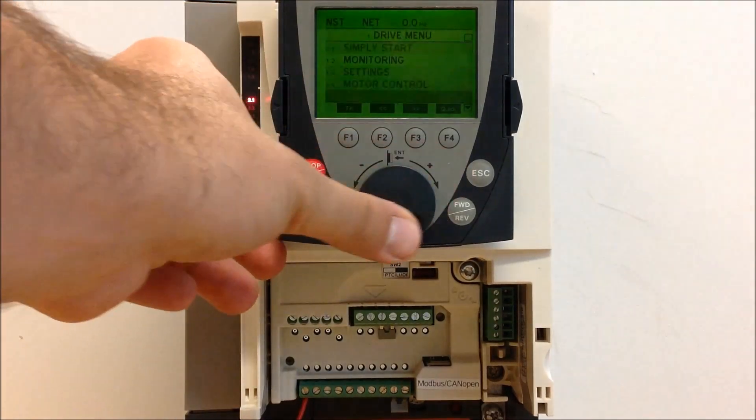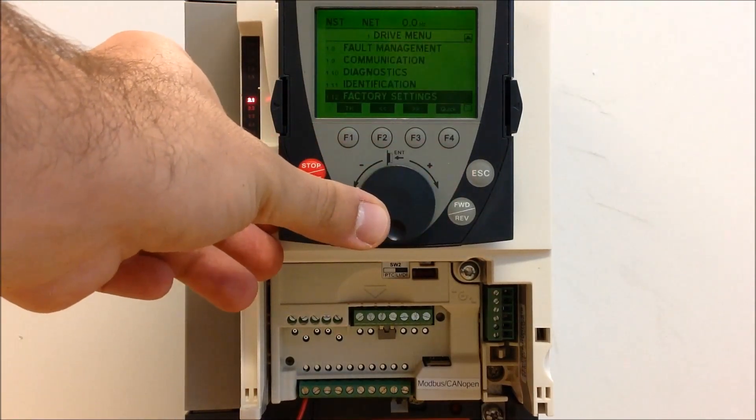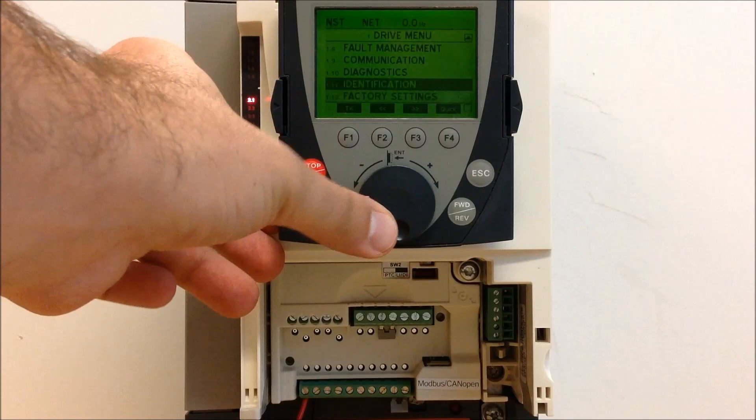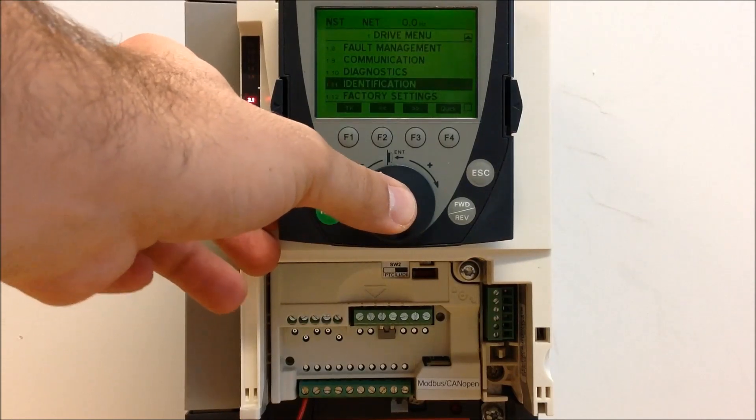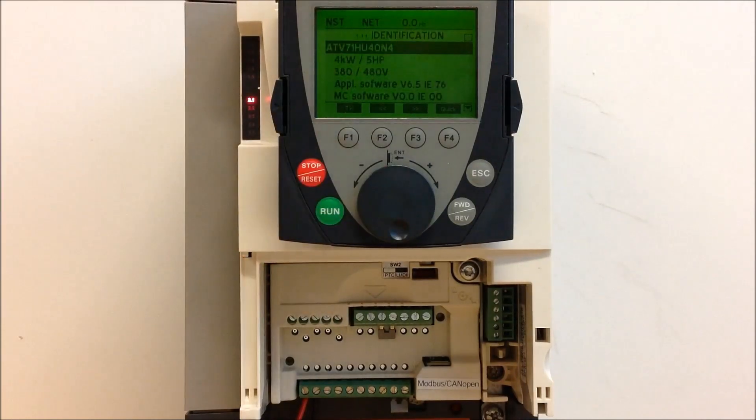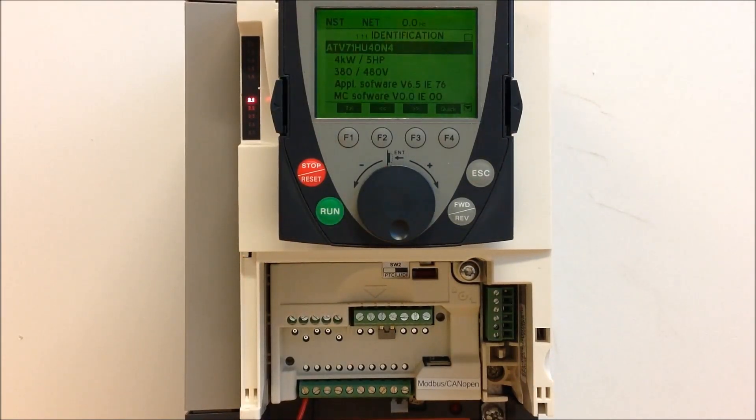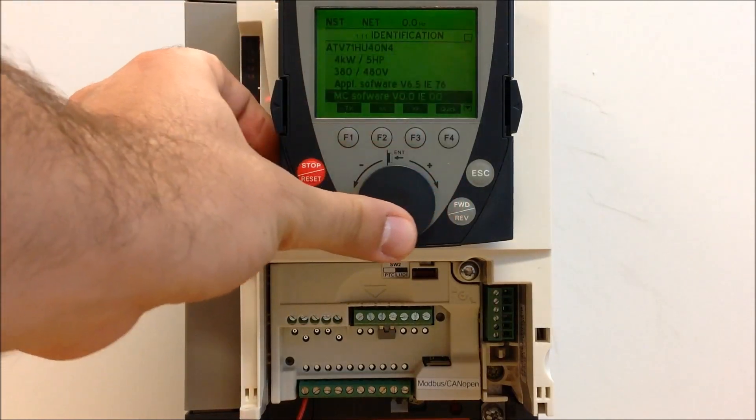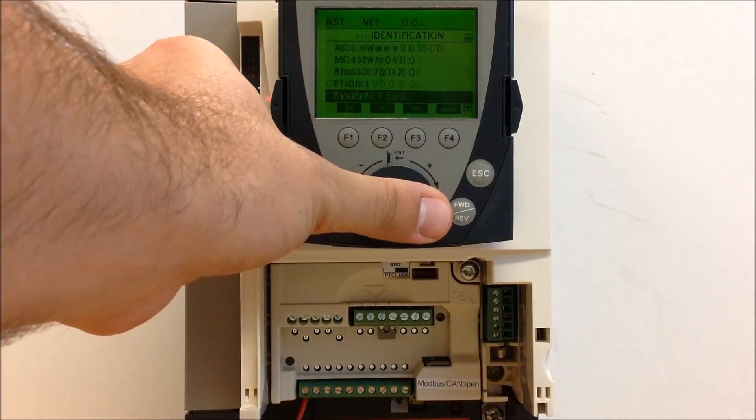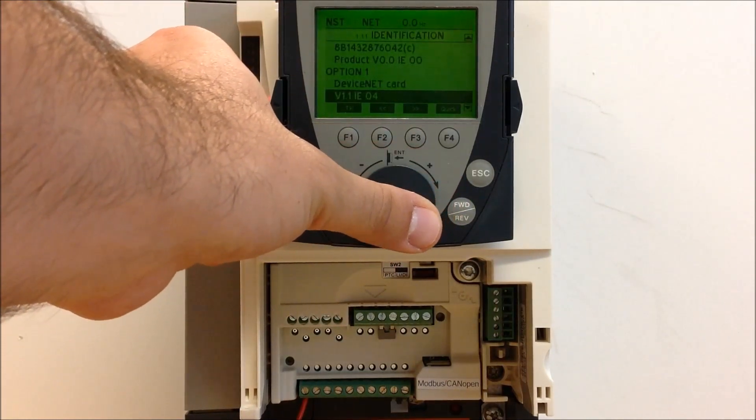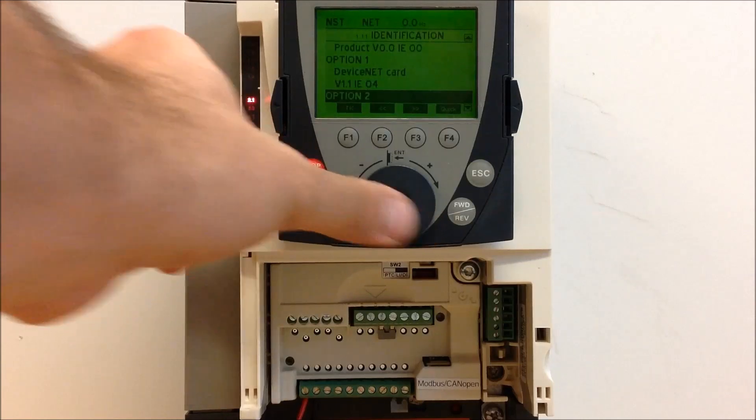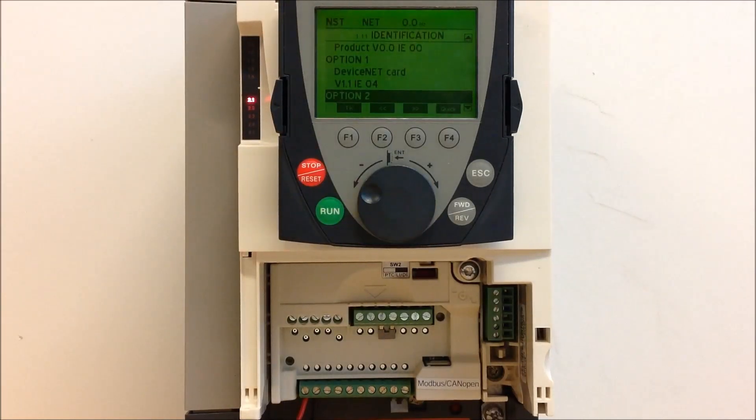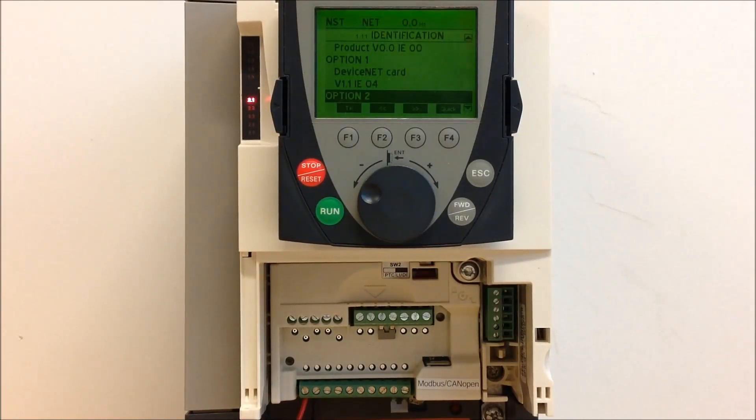Scroll down to 1.11 identification. Once you enter on this, you can scroll down until you see two things: option 1 and option 2. This is what the drive recognizes as your option cards.